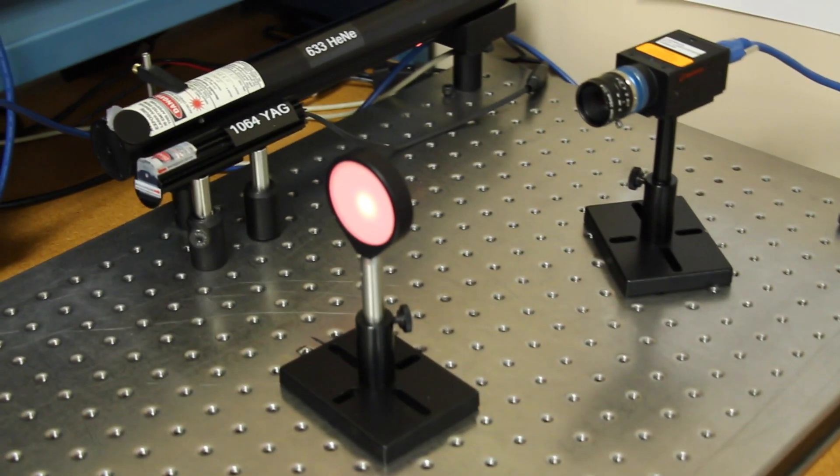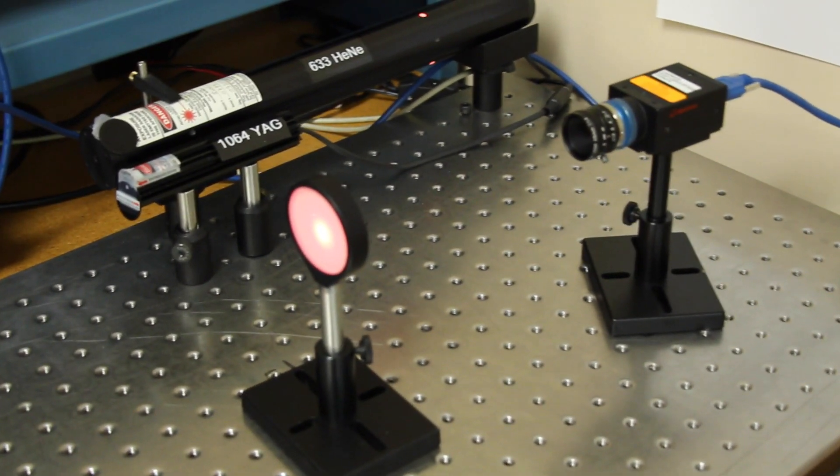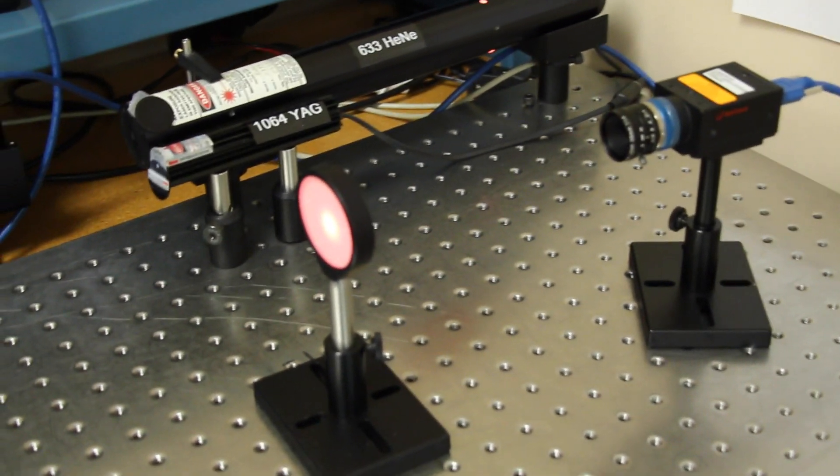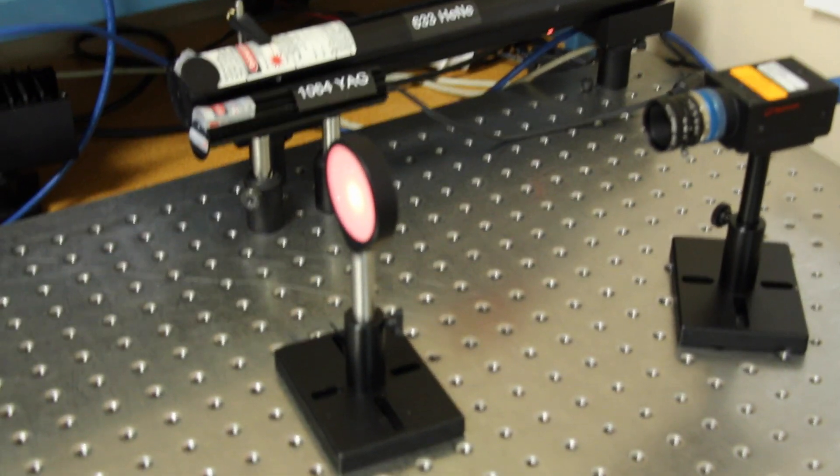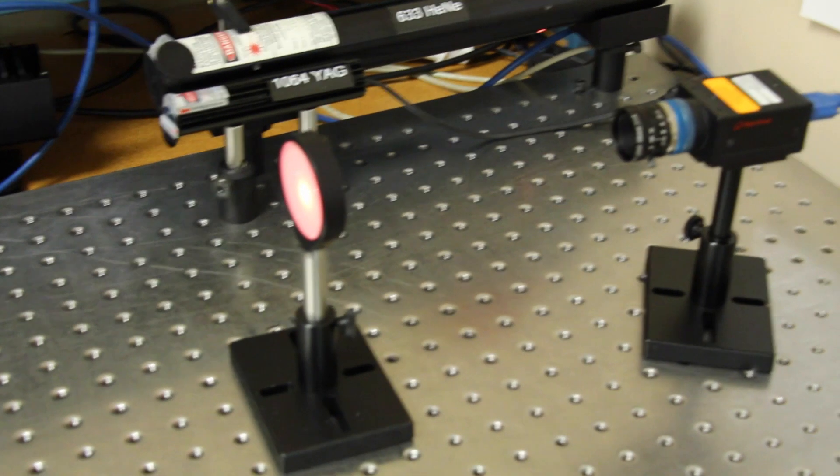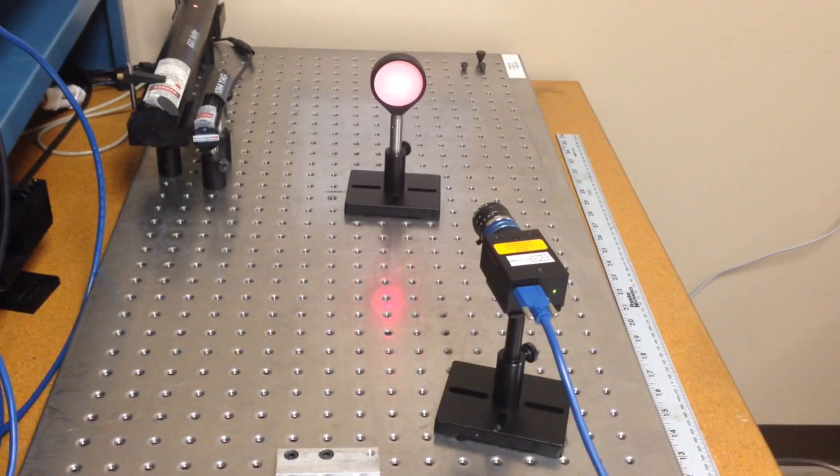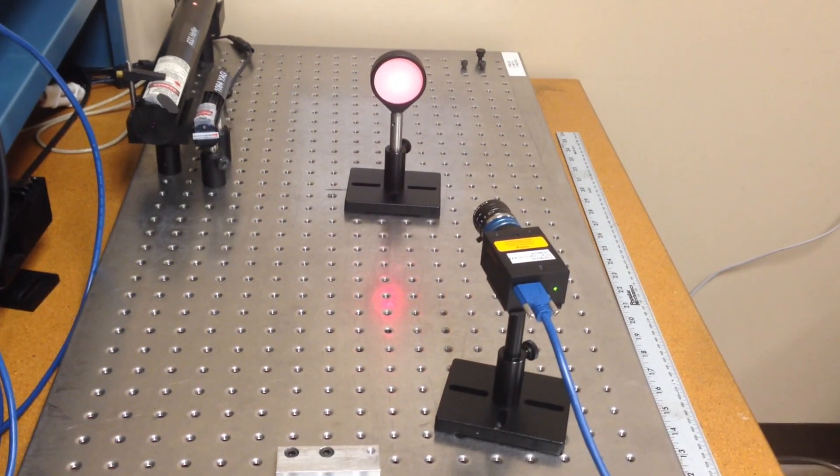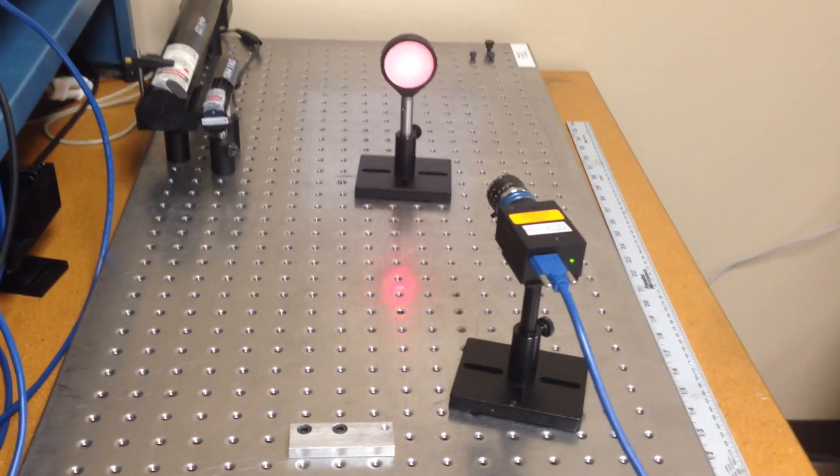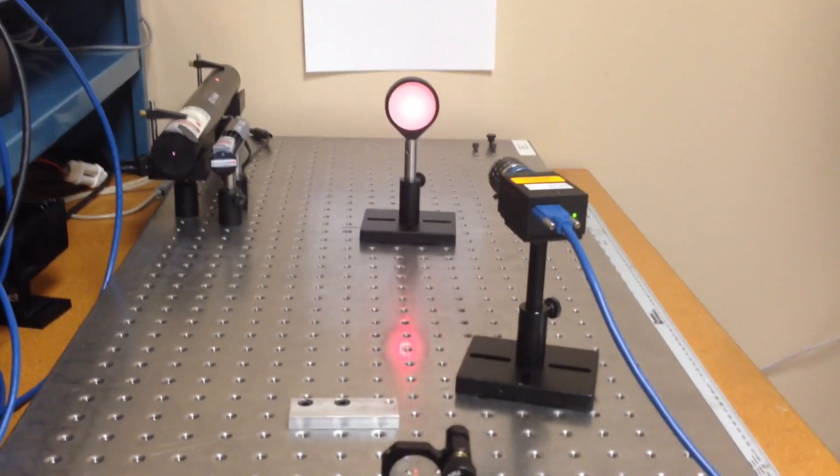In transmission mode, the camera imaging system should be placed slightly off-axis to the laser so that the transmitted laser beam does not impinge directly on the camera lens. In reflection mode, the laser and imaging system should be placed at small equal angles at either side of the central axis perpendicular to the target.